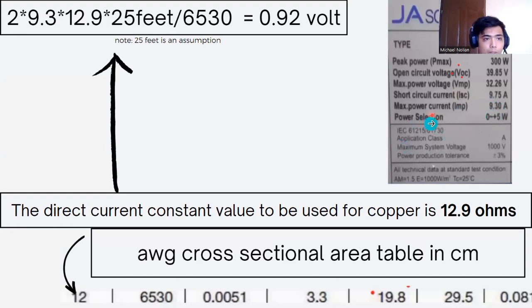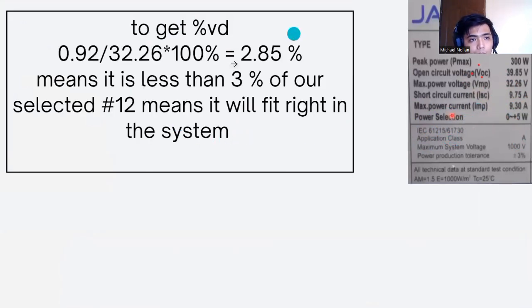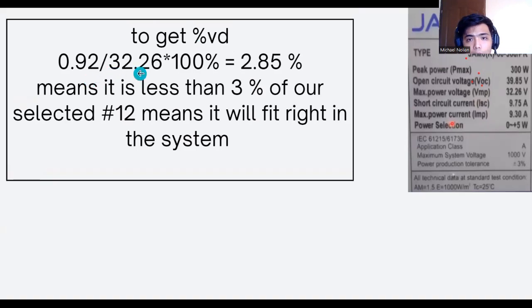Here. Then the 12. This 25 feet, if I remember correctly, is just an assumption; it is labeled as an assumption. Then this 9.3 is from JA Solar, from this table. You can see it there. I cannot read this one. So get the percentage of voltage drop: 0.92 divided by 32.26, multiplied by 100%.